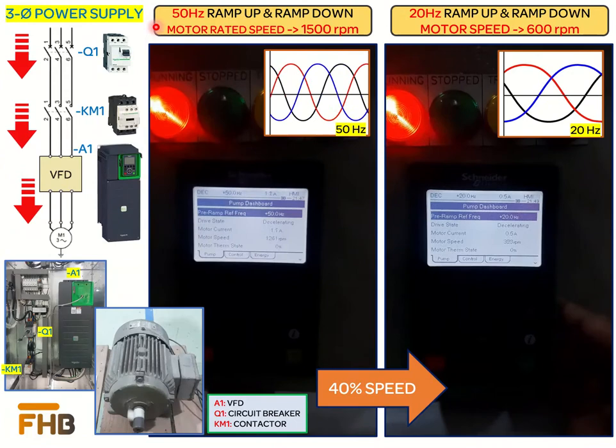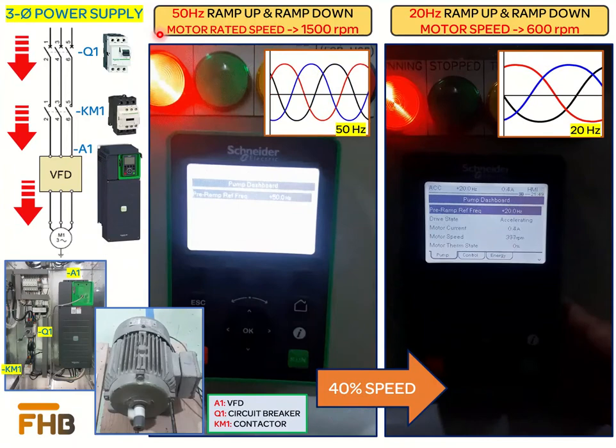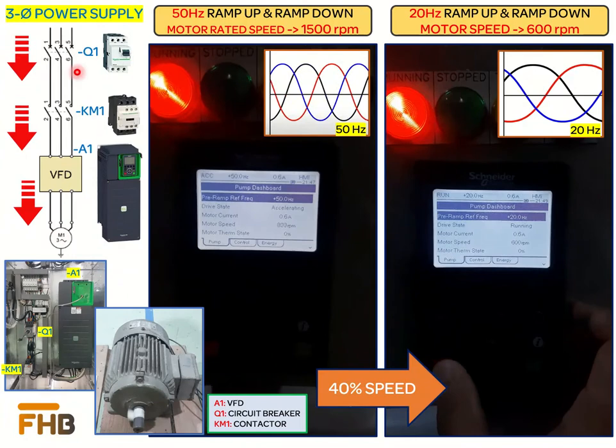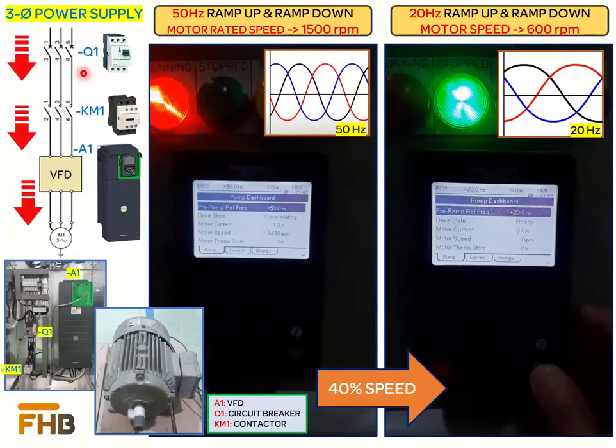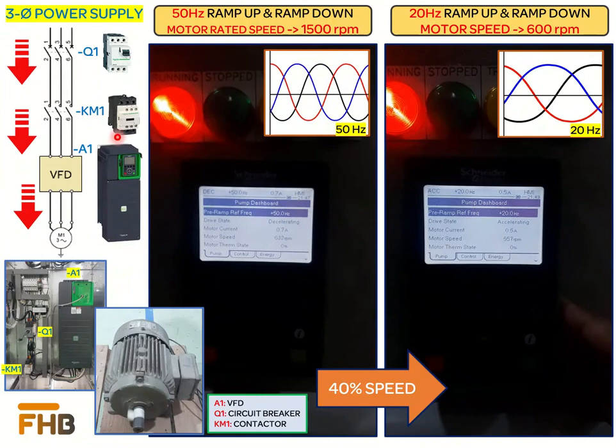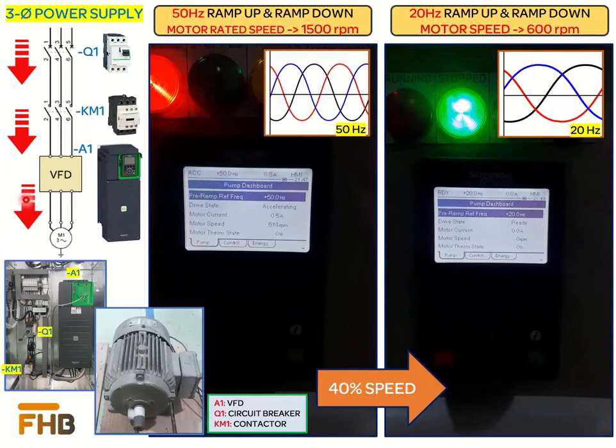We will now look at a demonstration where the VFD is controlling the speed of an induction motor. The induction motor used in this demonstration is rated at 50 Hz frequency and 1500 rpm speed. The power circuit consists of an incoming circuit breaker, which has a dual role: it can switch the incoming power to the VFD on and off, and it also provides short circuit protection to the complete power circuit, in addition to the built-in protection functions within the VFD. A power contactor in the circuit is operated based on the design control logic and decides when power will be supplied to the VFD, which then provides electrical power to the induction motor.